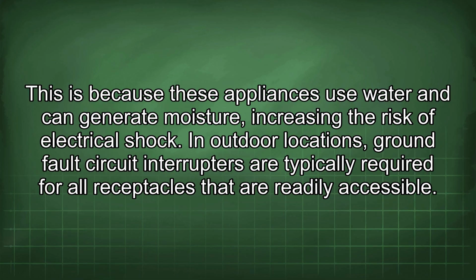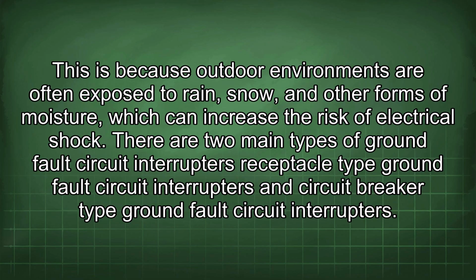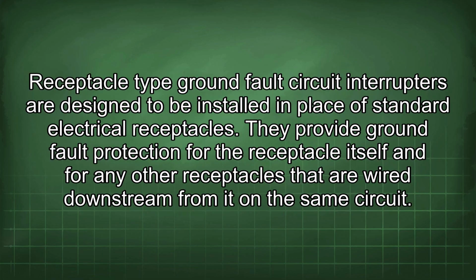In outdoor locations, ground fault circuit interrupters are typically required for all receptacles that are readily accessible. This is because outdoor environments are often exposed to rain, snow, and other forms of moisture, which can increase the risk of electrical shock. There are two main types of ground fault circuit interrupters: receptacle type ground fault circuit interrupters and circuit breaker type ground fault circuit interrupters. Receptacle type ground fault circuit interrupters are designed to be installed in place of standard electrical receptacles. They provide ground fault protection for the receptacle itself and for any other receptacles that are wired downstream from it in the same circuit.